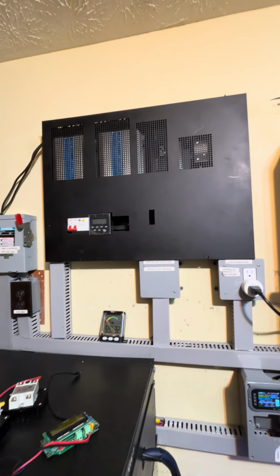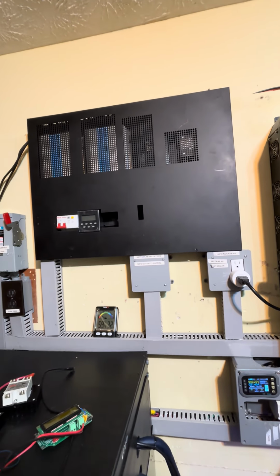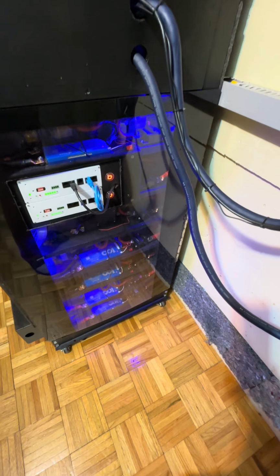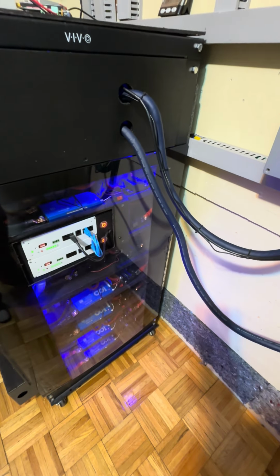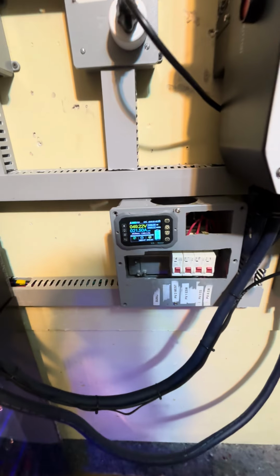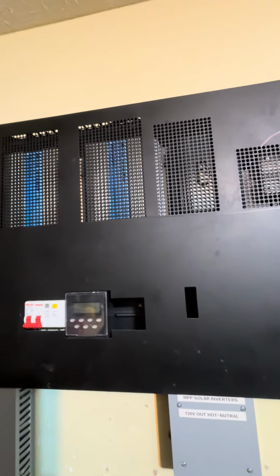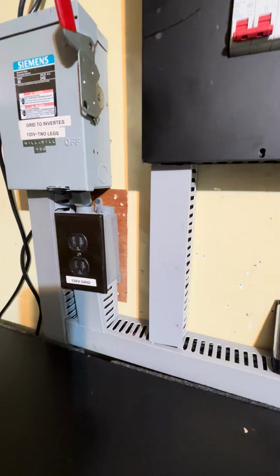Up here is my fail-safe dump load controller I'm also building out. In case any of these BMS fails for whatever reason and causes the inverter to keep charging or go over my set voltage of 50.2 volts, the trigger in here will trip it off the grid tie to dump the excess voltage.